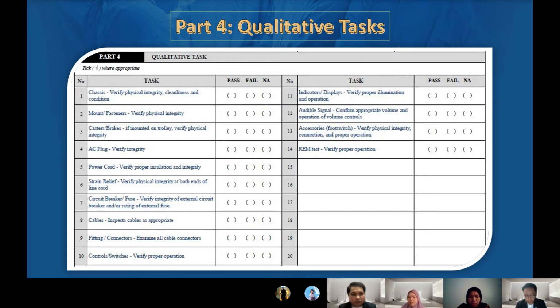If it's not in good condition, mark it as fail. For the controls and switches—the keypad on the ESU—press it to check it's working and shows the correct setting, like pressing mono and seeing the mono mode and its range displayed.